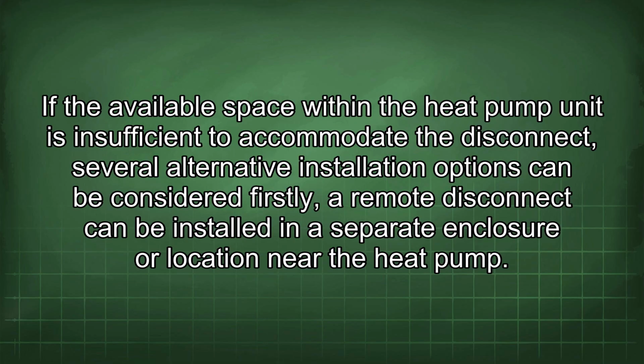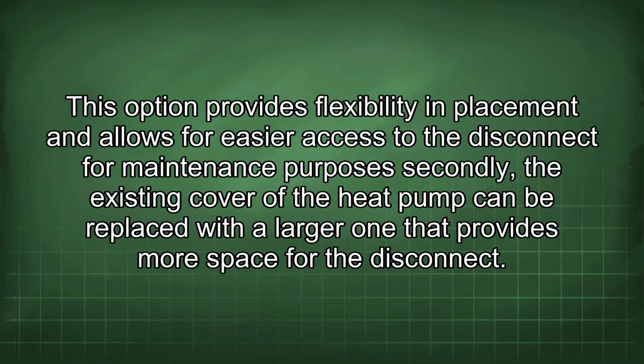If the available space within the heat pump unit is insufficient to accommodate the disconnect, several alternative installation options can be considered. Firstly, a remote disconnect can be installed in a separate enclosure or location near the heat pump. This option provides flexibility in placement and allows for easier access to the disconnect for maintenance purposes.